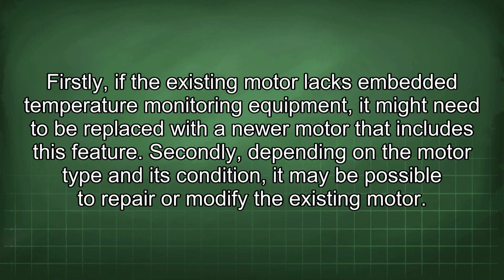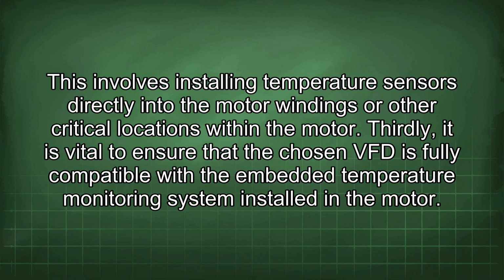Firstly, if the existing motor lacks embedded temperature monitoring equipment, it might need to be replaced with a newer motor that includes this feature. Secondly, depending on the motor type and its condition, it may be possible to repair or modify the existing motor. This involves installing temperature sensors directly into the motor windings or other critical locations within the motor.